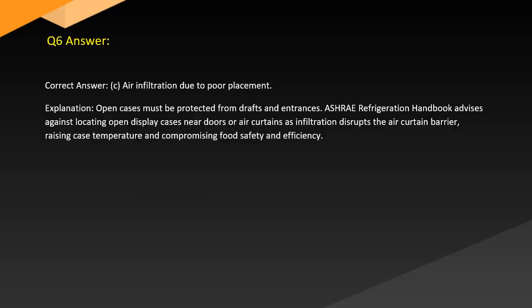Answer. Correct answer, C. Air infiltration due to poor placement. Explanation: open cases must be protected from drafts and entrances. ASHRAE Refrigeration Handbook advises against locating open display cases near doors or air curtains, as infiltration disrupts the air curtain barrier, raising case temperature and compromising food safety and efficiency.